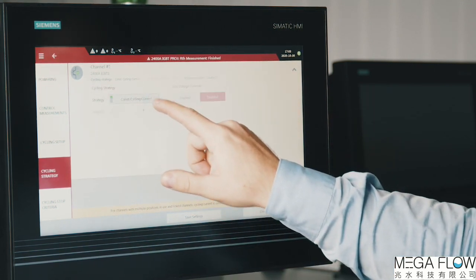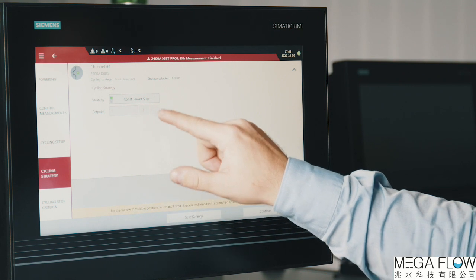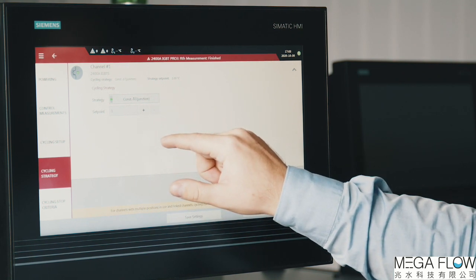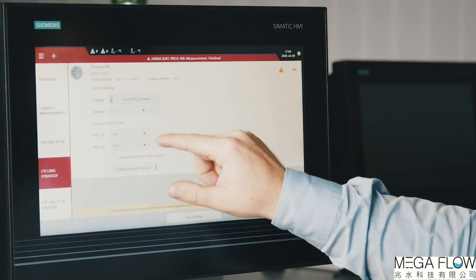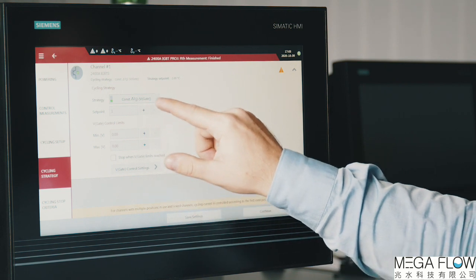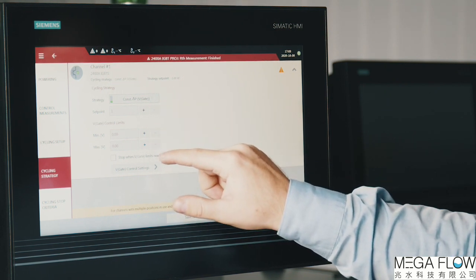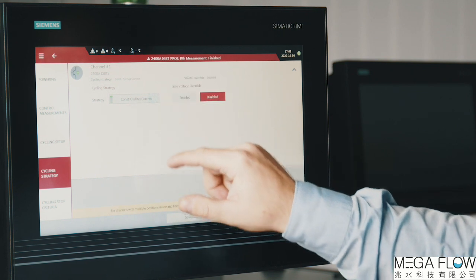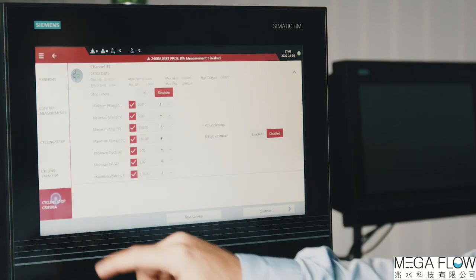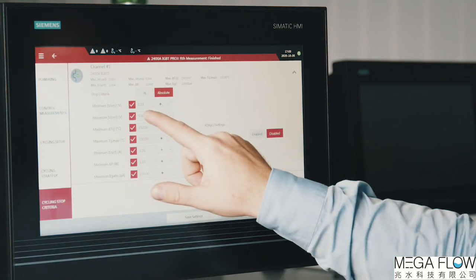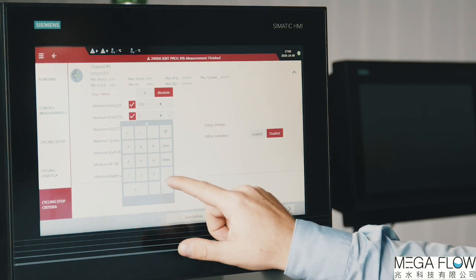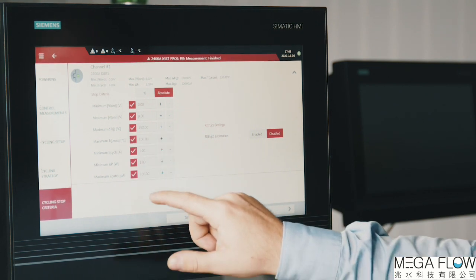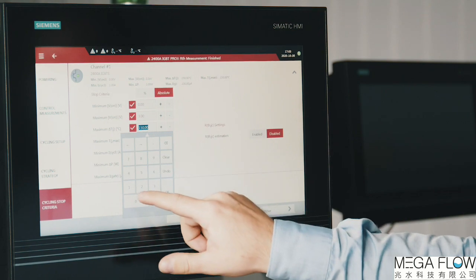Current testing guidelines prescribe using fixed heating current independent of the device degradation to best mimic the real usage of the components, but there are optional methods to ensure constant junction temperature change or constant power step by regulating the heating current or gate voltage as well. Finally, the cycling stop criteria needs to be defined. The system monitors several parameters in each cycle, and if they exceed a certain threshold, the cycling is stopped automatically.